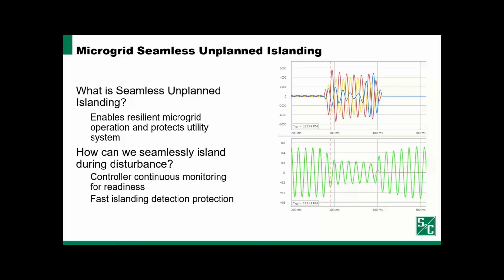In this event, the local customers didn't even know that a fault occurred. The lights may have dimmed for a brief moment, but we recover seamlessly to an unplanned islanding condition where the DERs have disconnected to de-energize the fault, but also maintained islanded operation.